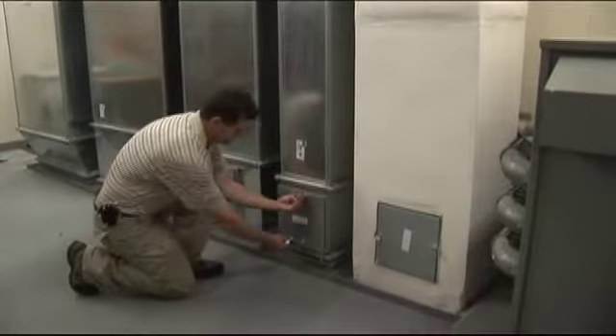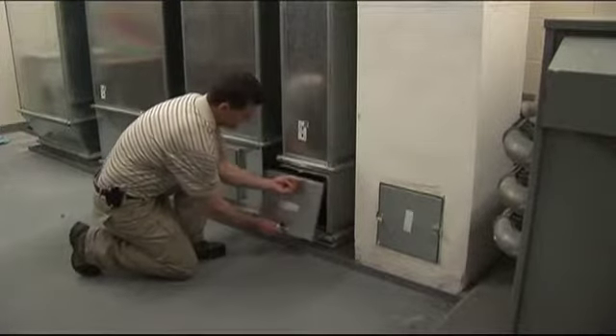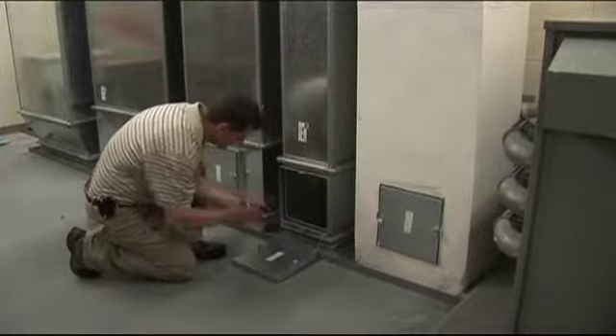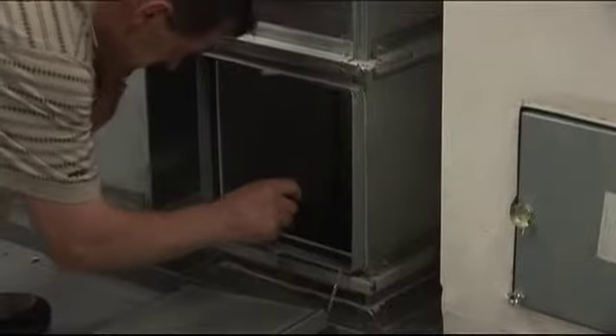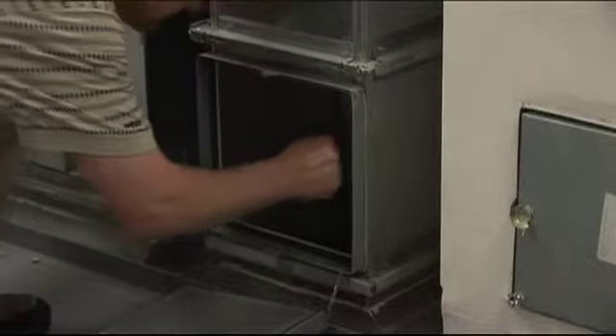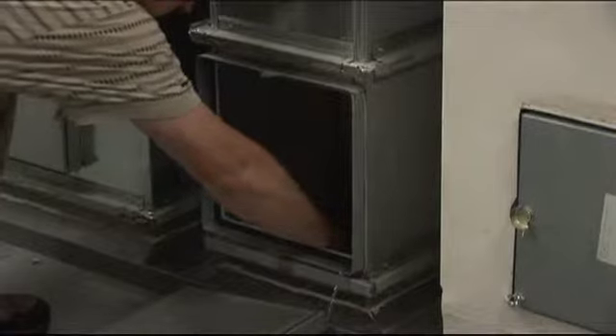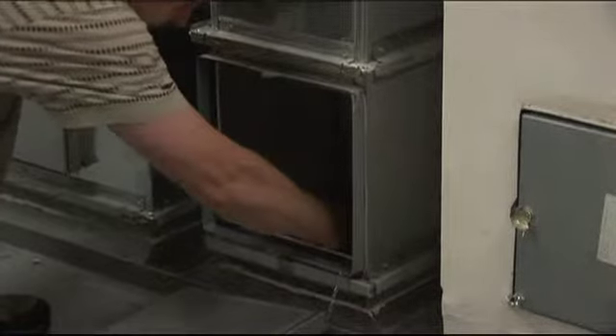Fire dampers may be installed in the mechanical ventilation ductwork. In an emergency, these dampers close to prevent smoke and fire from entering from another zone. Air handling systems are also usually designed to shut down in a fire emergency to prevent the spread of smoke and fire.